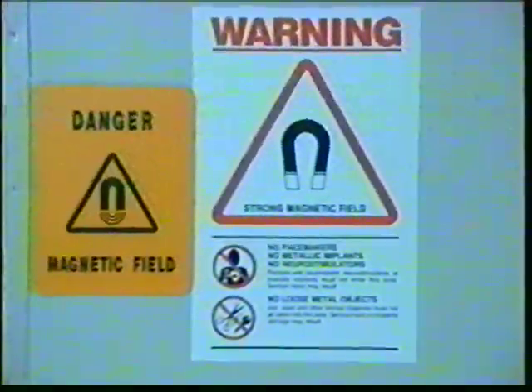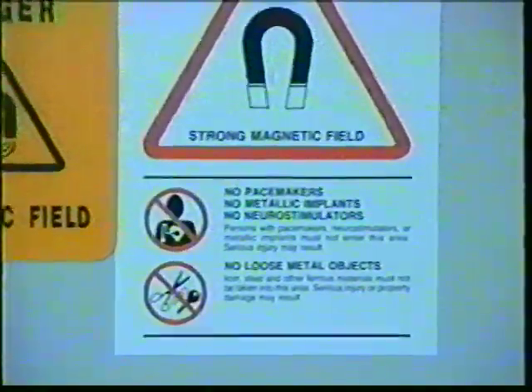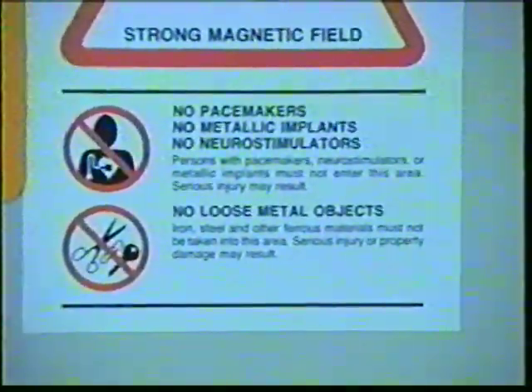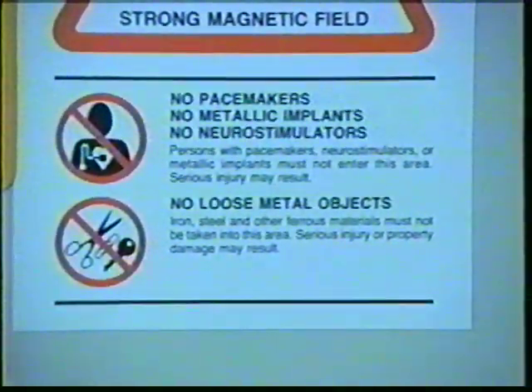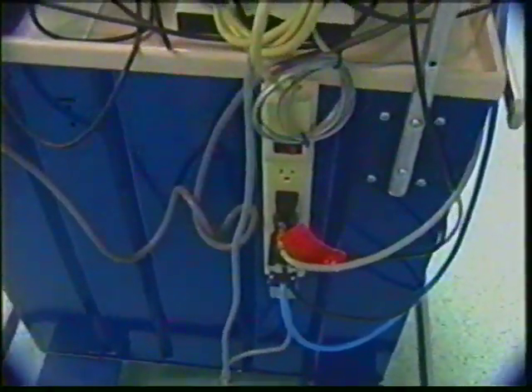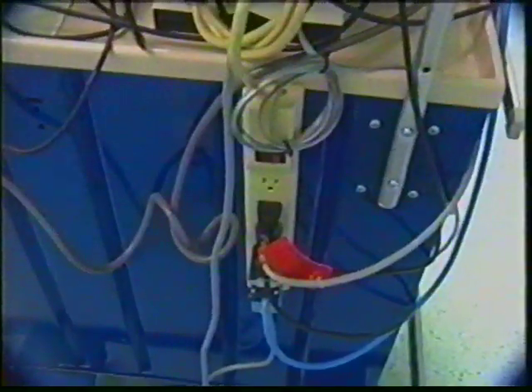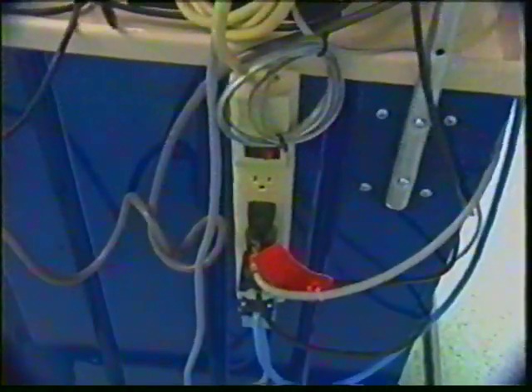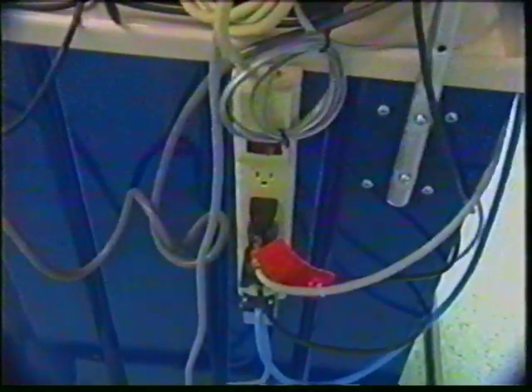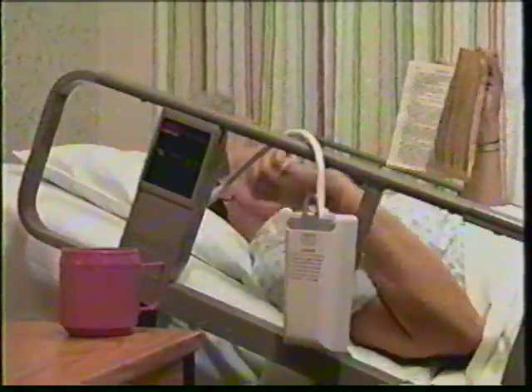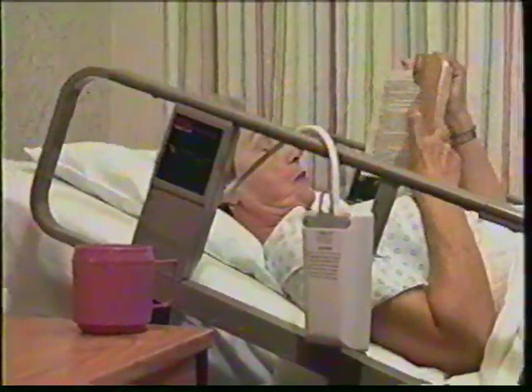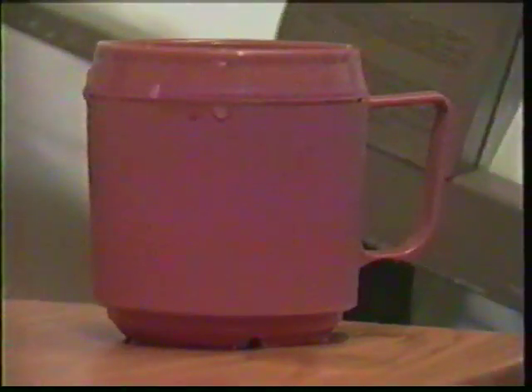Post warnings for patients with pacemakers in areas that contain equipment such as microwave ovens that may produce electromagnetic interference. Before using convenience receptacles that come installed in some appliances and furniture, be sure they are safe for use in healthcare facilities. Use caution if your facility has older electrically operated beds that use portable control units. In case of incontinence or spills, a control unit could be hazardous, especially if it is in bed with the patient.